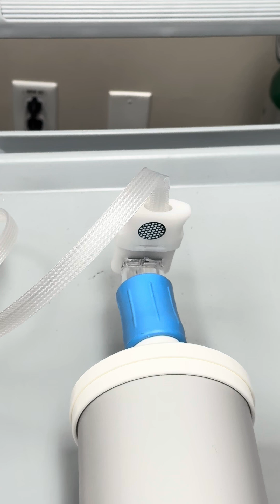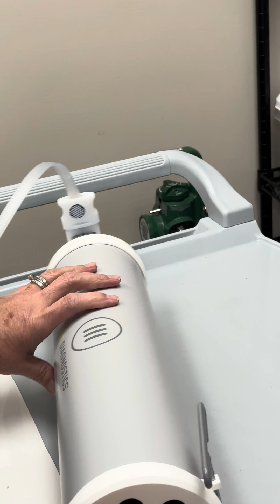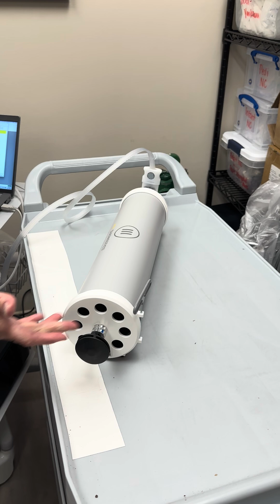So easy to remember. So for purposes of calibration, the syringe is our patient, so I have that facing there. I like to start, because these are new syringes, I just want to give this a couple of withdrawals and injects just to make sure that the plunger is moving smoothly, it's not sticking. So I've already zeroed the flow, so now I can either click on the start button or I can use the space bar to start, and I'm going to follow these prompts to withdrawal. I'm going to pause until I see the word inject appear, and then I'll push the plunger in.